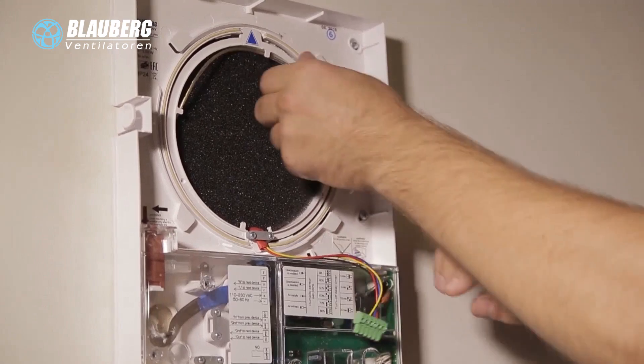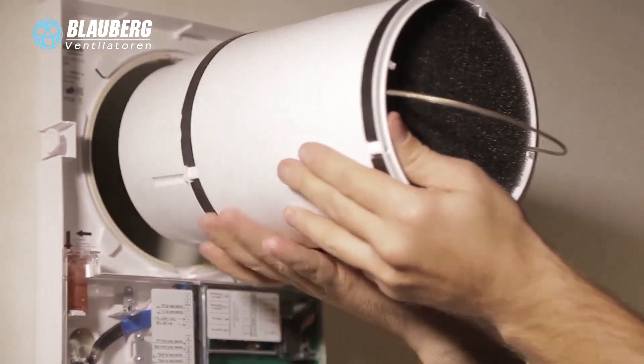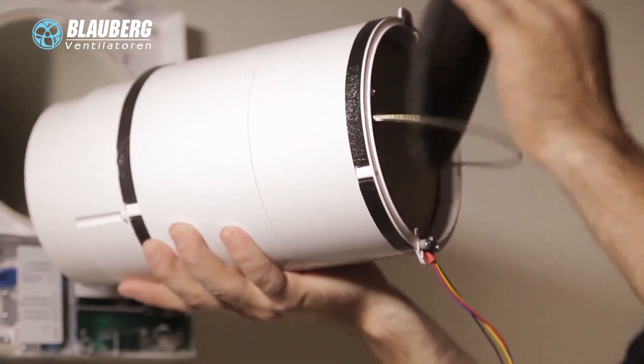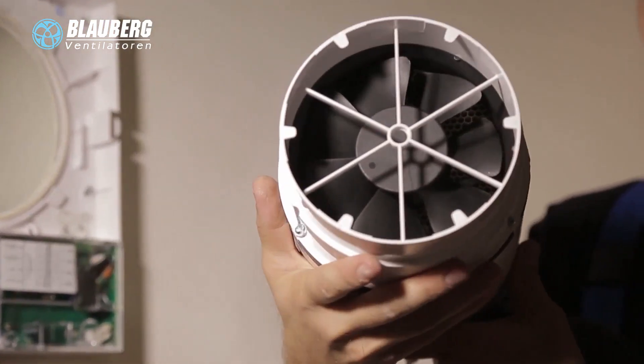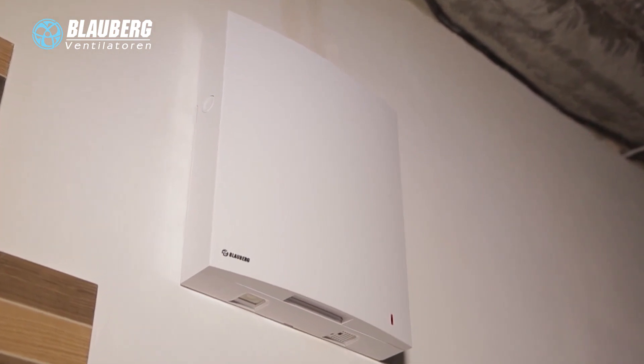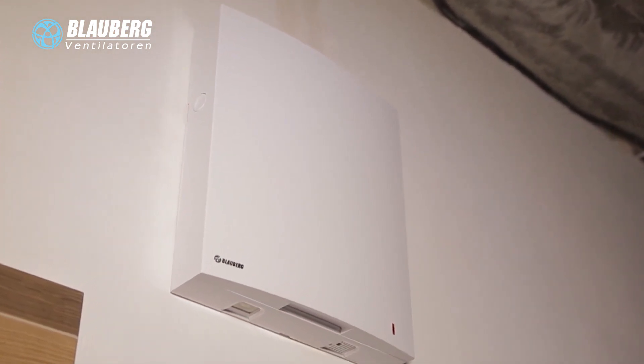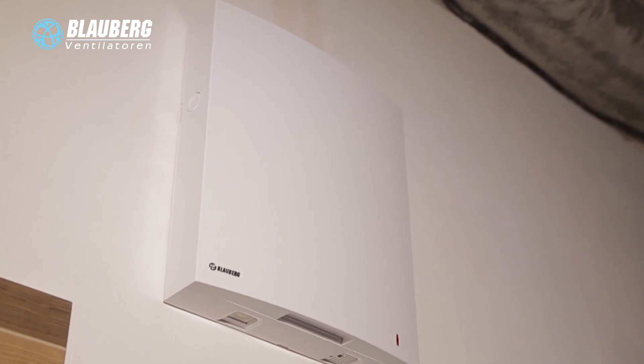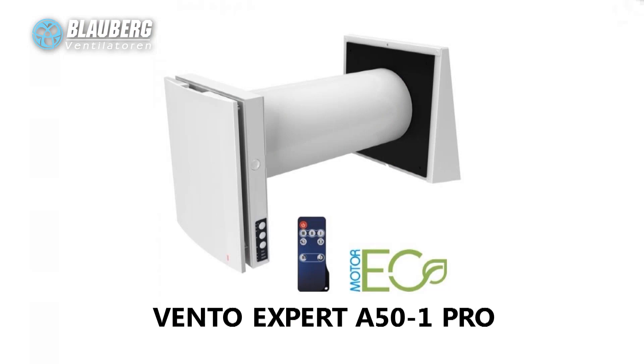Remove the socket connector from the control board. Pull the cord to remove the cartridge from the air duct. Remove the filters from the cartridge. Clean the filters as required — flush the filters with water, let them dry out, and install the dry filters back into the air duct. The Vento Expert single room reversible ventilation unit with energy regeneration is a perfect solution to create a comfortable indoor microclimate and efficient single room supply and exhaust ventilation.